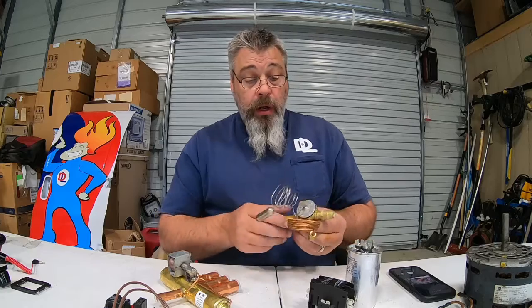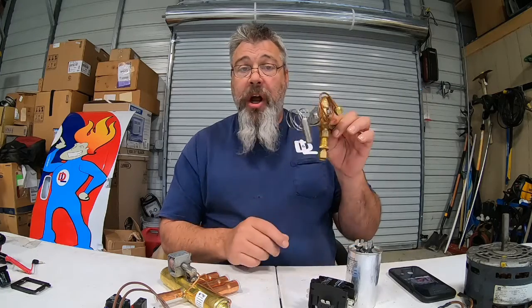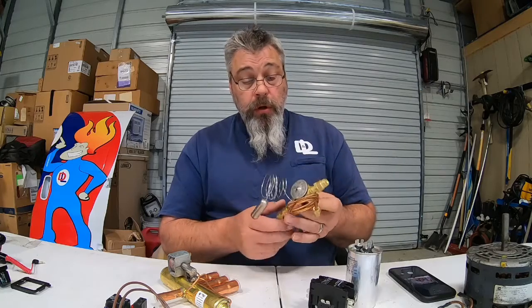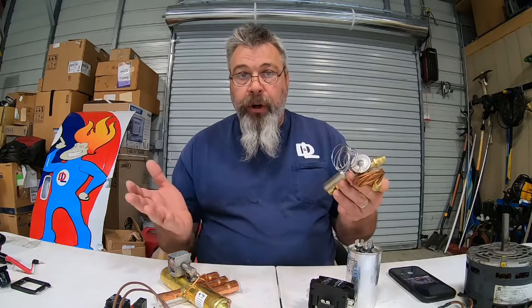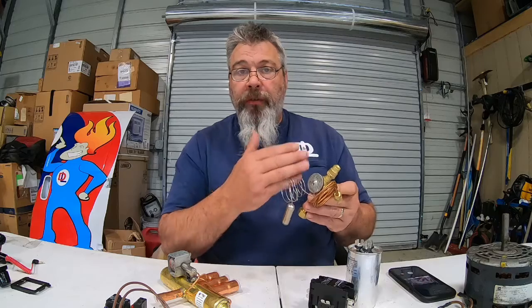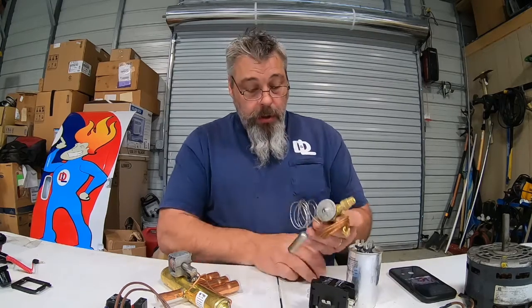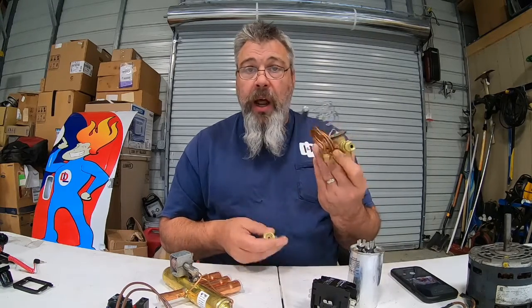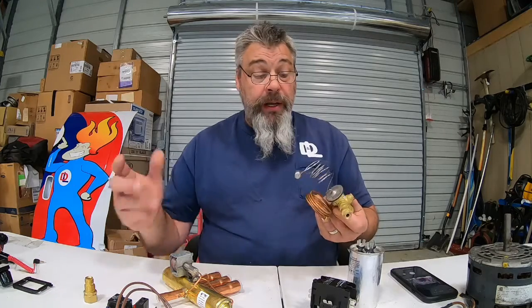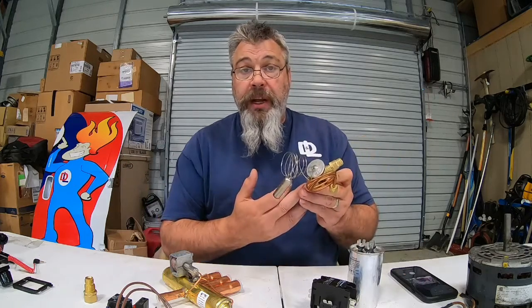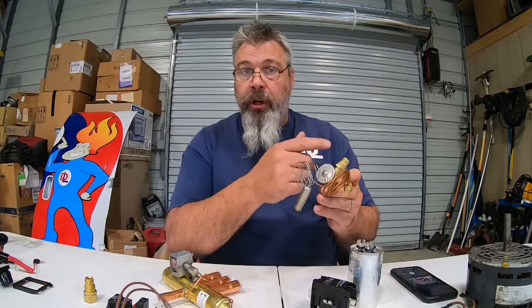You cannot get any type of adjustment out of it. However, manufacturers are now putting in what they call TXVs, a thermal expansion valve. Some refer to it as just a metering device. It meters the flow of refrigerant, okay? So we'll have one on the outside and one on the inside. And what that does is that refrigerant comes in and changes state through that metering device.